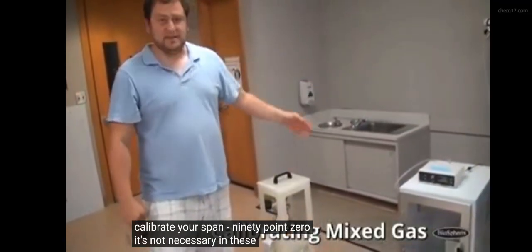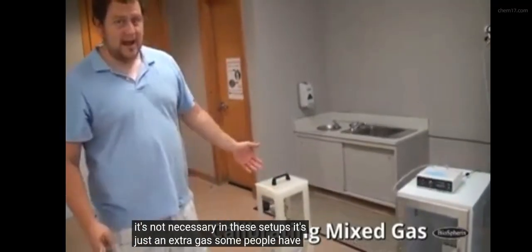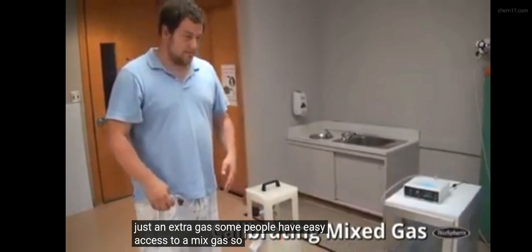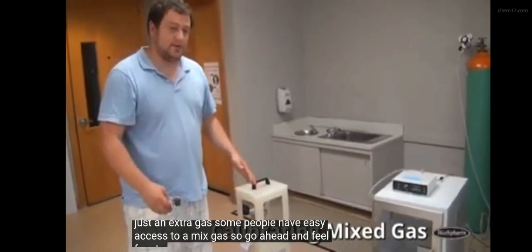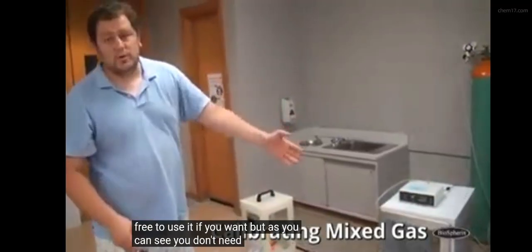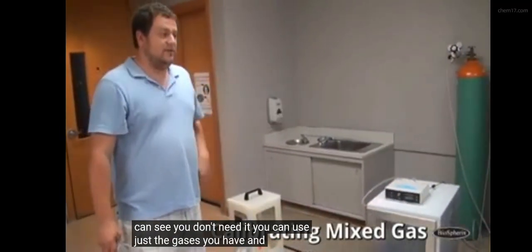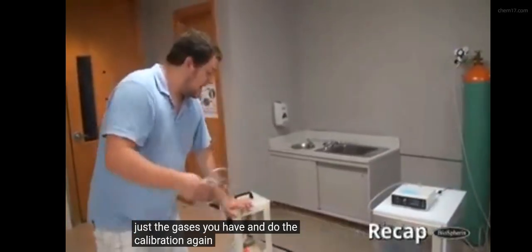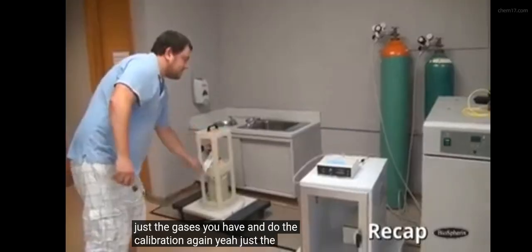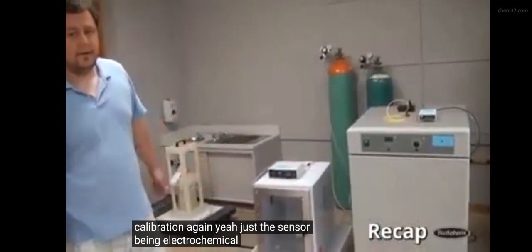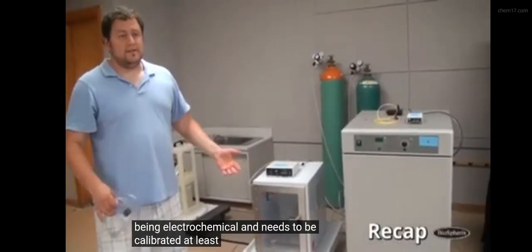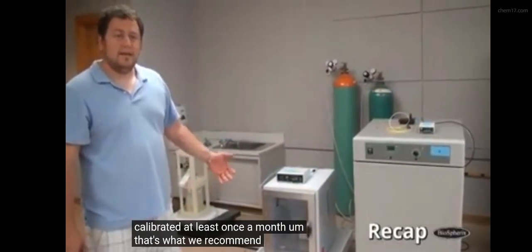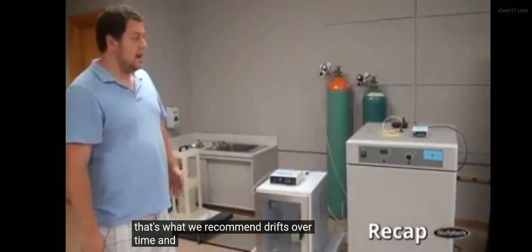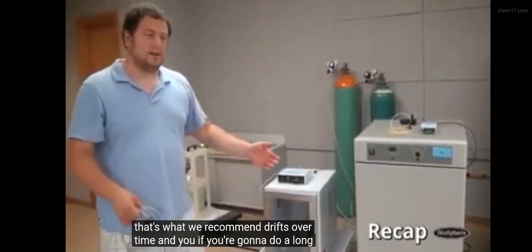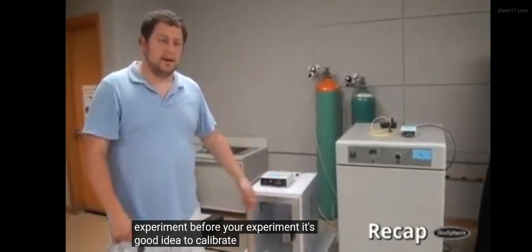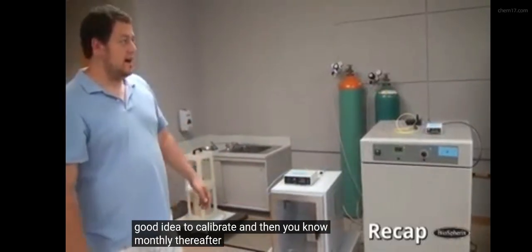It's not necessary in these setups. It's just an extra gas. Some people have easy access to a mixed gas, so go ahead and feel free to use it if you want, but as you can see, you don't need it. You can use just the gases you have and do the calibration. Again, just to recap, the sensor being electrochemical, it needs to be calibrated at least once a month. That's what we recommend. It drifts over time, and if you're going to do a long experiment, before your experiment, it's a good idea to calibrate, and then monthly thereafter.